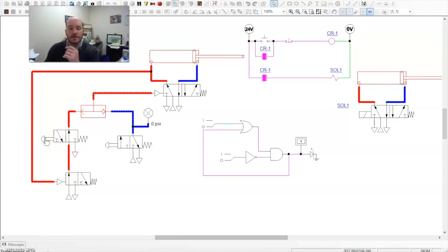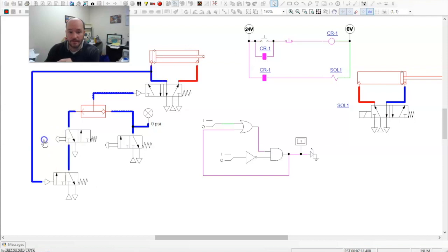So it's the push button or memory, not the stop button. Okay. So now when I activate this normally open 3-2 valve, it's going to close it, shutting it off. So when I activate this, it retracts because we lose pressure here. So the spring over here overcomes this. So no air can flow through here anyway. That disengages it, retracting the cylinder.